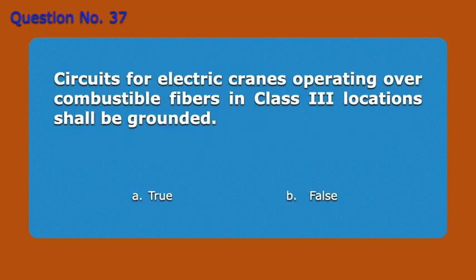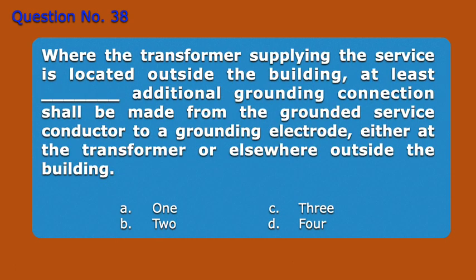Question number 37. Circuits for electric cranes operating over combustible fibers in Class 3 locations shall be grounded. A, true. B, false. Answer B, false. Question number 38. Where the transformer supplying the service is located outside the building, at least blank additional grounding connection shall be made from the grounded service conductor to a grounding electrode, either at the transformer or elsewhere outside the building. A, 1. B, 2. C, 3. D, 4. Answer A, 1.